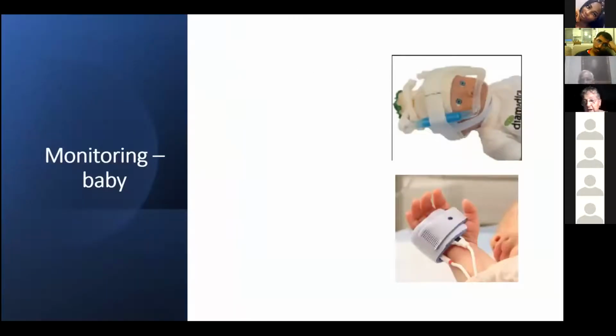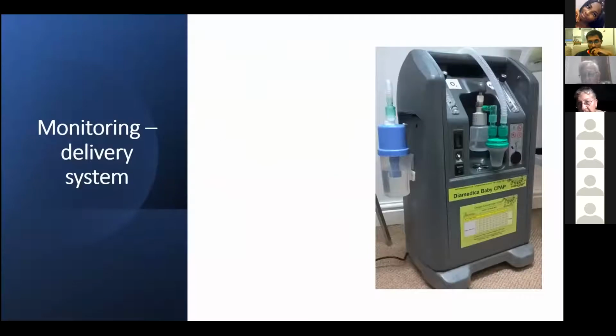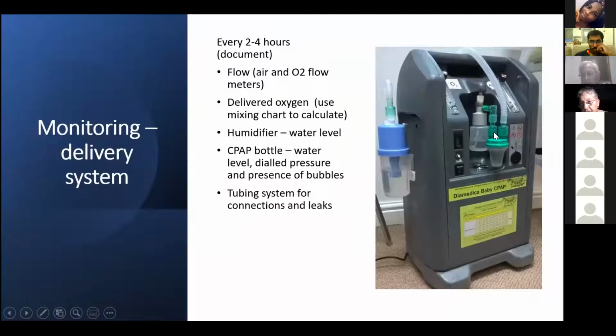Make sure that the saturation monitor is properly placed on the hand, and that the device on the baby's head on the CPAP is correct. This is a Hudson prong, and you are using the RAM cannulas, but the important thing is that we have all the tubes in place. So remember also that you want to make sure, as I said, when the baby is not improving, that you don't have any technical problems. If the amount of fluid in the CPAP bottle is not enough, if the humidity is not enough, if any of these pipes is disconnected, the baby will not improve, and you will wonder why it's not improving, although he has a disease that now by day 2 should improve.